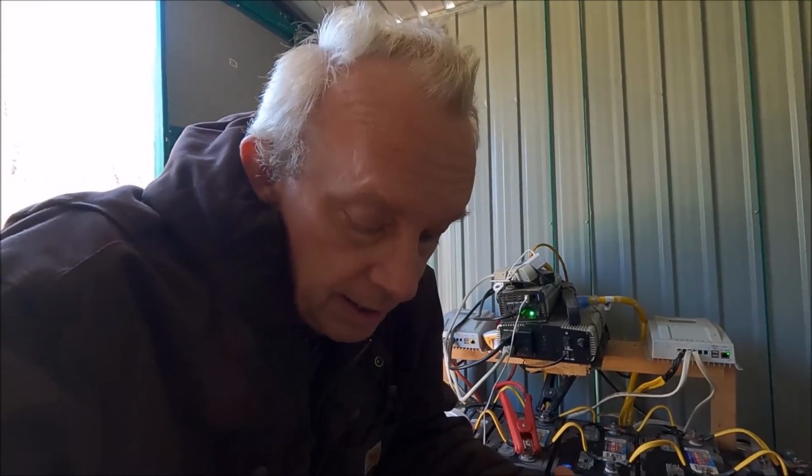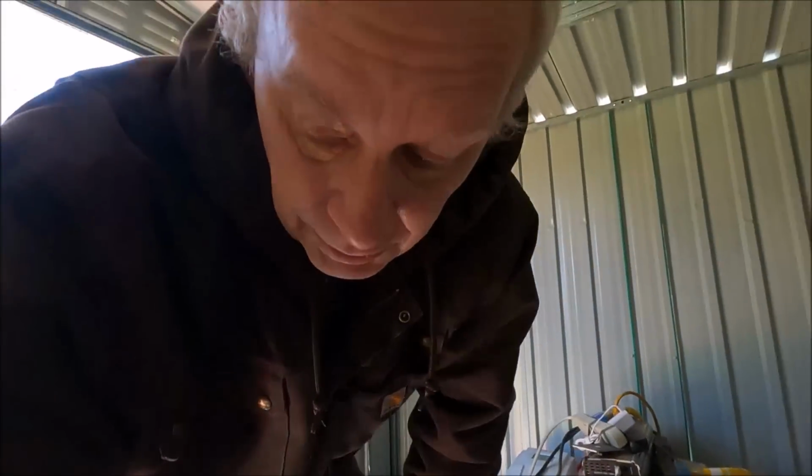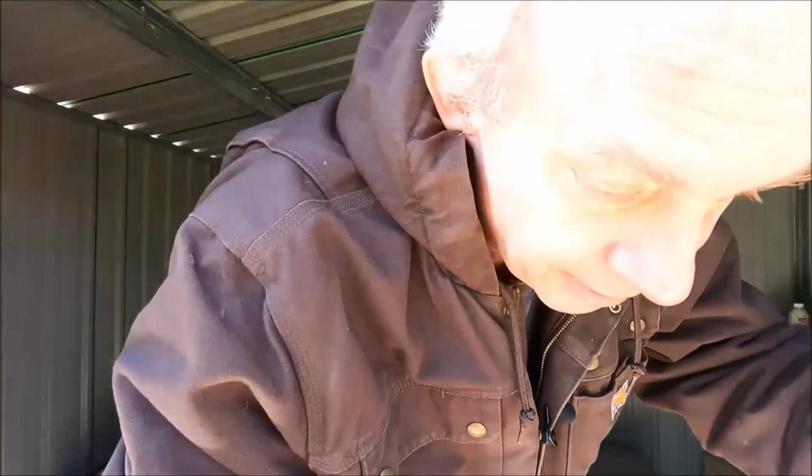If it's not bad, then I cover it up. I expose another panel. And if I get any amps out of that, then I know that one's not bad. And I just keep continuing until I find one producing 0 amps. Well, I walked outside to grab a cover and I instantly saw what happened. It's the first time it's been this easy, to be honest.